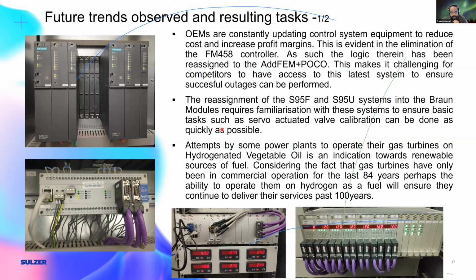Yeah. Now, you can also see what was done for the main controller has also been done for the protection system. So you do not have your classic 95F, 95U protection systems. They are now outsourced into the Braun modules. So now this Braun module has the capability not only to measure the speed of the turbine. So you see, again, channel A and channel B to each module. So you have 3 for the speed measurements and 3 for the protection. So it means now you have the whole protection system, which used to be a whole cabinet, being compacted into one rack. And this is the way forward. Systems are being put together, being compacted in order to reduce cost of production and increase profit margins. And then you see this picture is actually of the Argos OMDS.